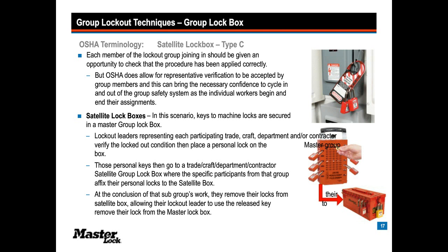In a satellite lockbox, the primary lockout leader goes through and locks out the machine according to the procedure. A verifier goes through and verifies the lockout according to the procedure. It may be other trade groups want to send representatives through and verify the procedure has been properly applied.